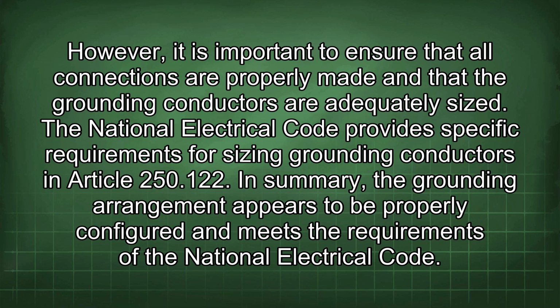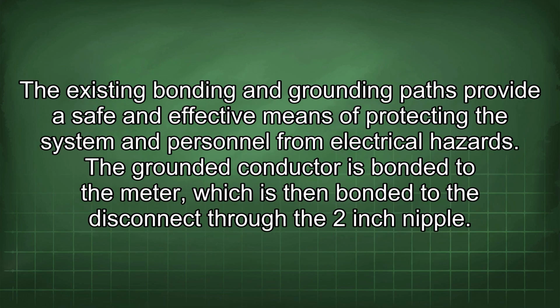However, it is important to ensure that all connections are properly made and that the grounding conductors are adequately sized. The National Electrical Code provides specific requirements for sizing grounding conductors in Article 250.122. In summary, the grounding arrangement appears to be properly configured and meets the requirements of the National Electrical Code. The existing bonding and grounding paths provide a safe and effective means of protecting the system and personnel from electrical hazards.